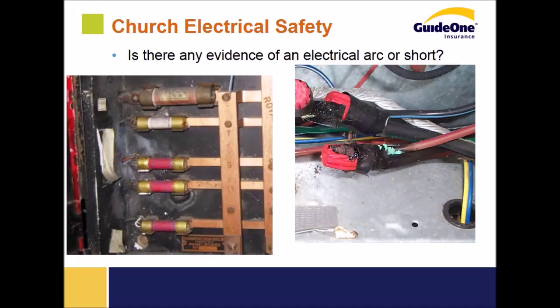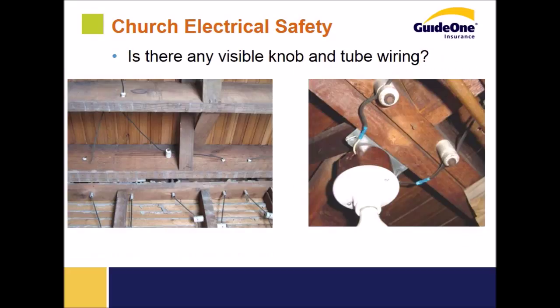In the image on the left, you see some charring, some evidence of a flash by those middle cartridge fuses. Then in the image on the right, you see obvious melting of the insulation. You see some corrosion, and again, that's why we have an electrician come in.